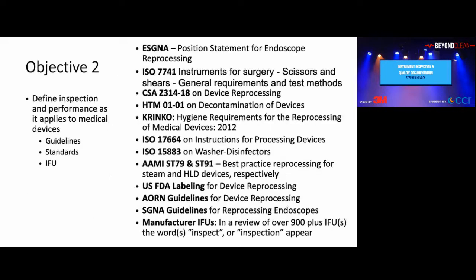Objective 2: define inspection and performance as it applies to medical devices, guidelines, standards, and IFU. If you look over to the side of this slide, since I know we have an international audience, I've tried to give different standards that are out there. There's the EU standard for endoscope reprocessing. Did you know there's an ISO standard, 7741, for scissors and shears that tells you what type of test you should use to make sure your scissors are sharpened? For those of you in Canada, Z314.18 on device reprocessing. Or in England, HTM 01-01 on decontamination of devices. You have different ISO standards, 15883 for washers.